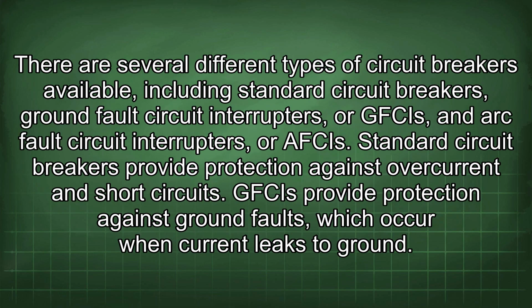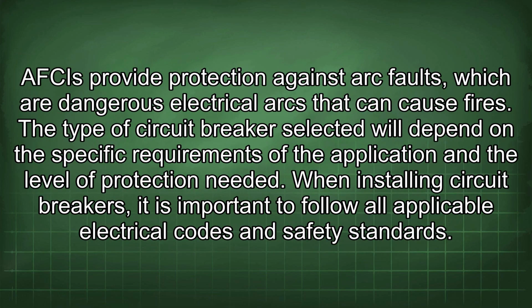There are several different types of circuit breakers available, including standard circuit breakers, ground fault circuit interrupters, or GFCIs, and arc fault circuit interrupters, or AFCIs. Standard circuit breakers provide protection against overcurrents and short circuits. GFCIs provide protection against ground faults, which occur when current leaks to ground. AFCIs provide protection against arc faults, which are dangerous electrical arcs that can cause fires.